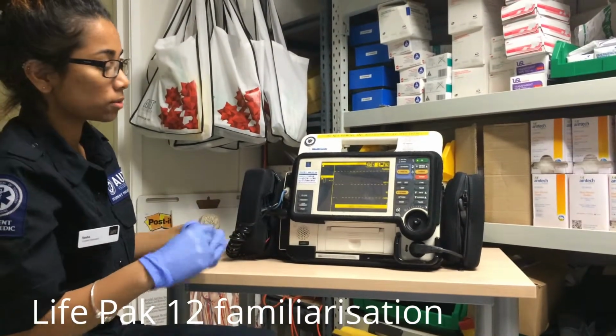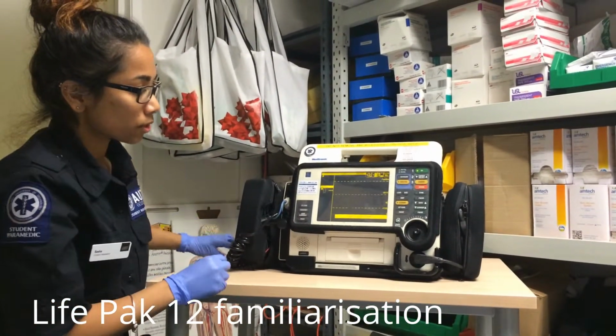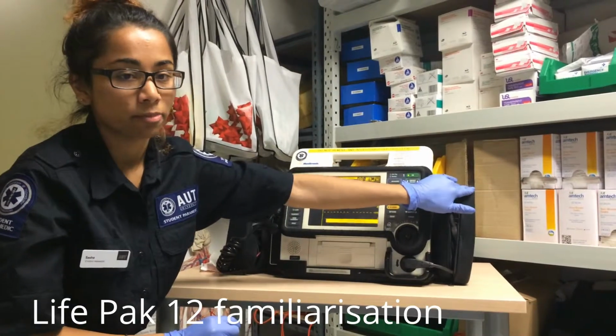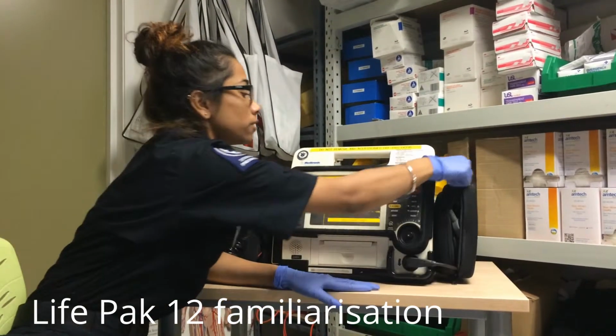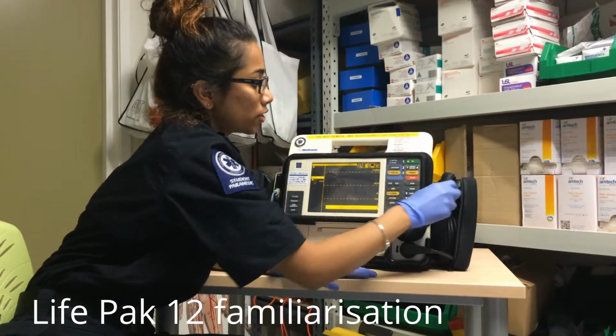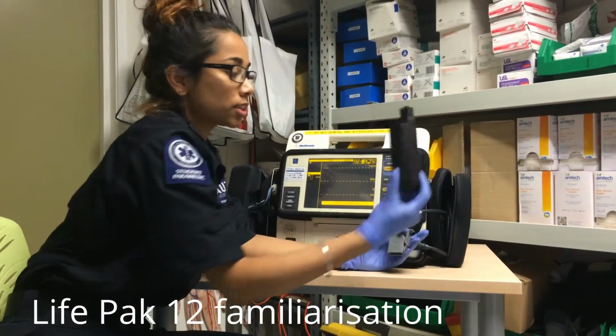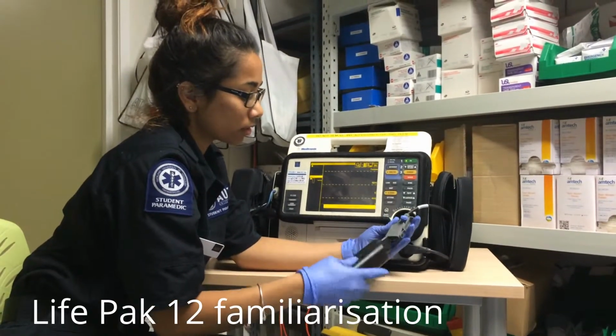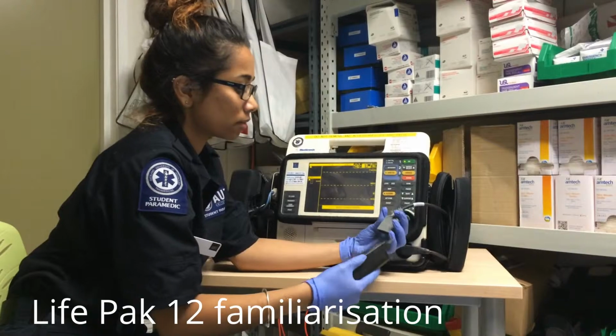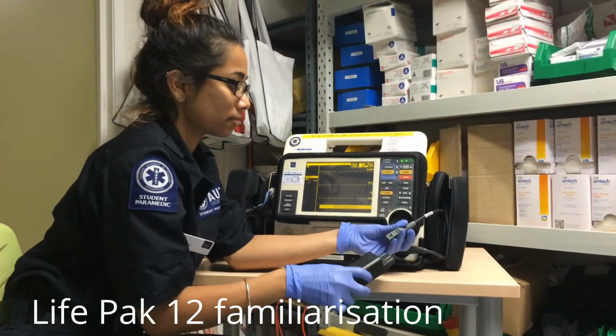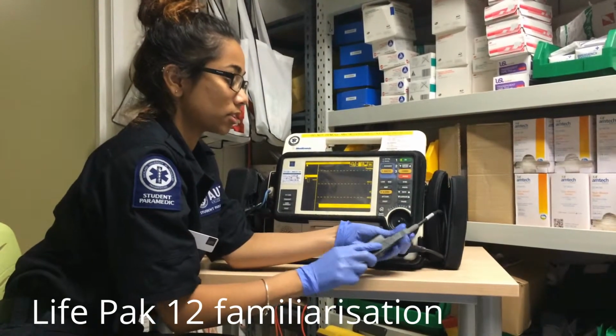So we also want to do a test defibrillation. So the left hand side of the LifePak 12 is the defib side. So we want to attach our defib to a test load.